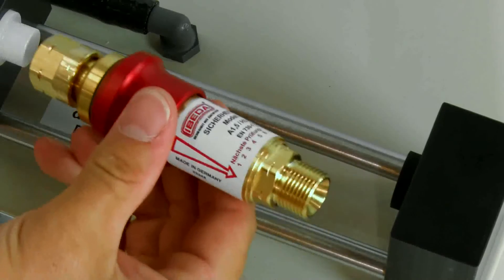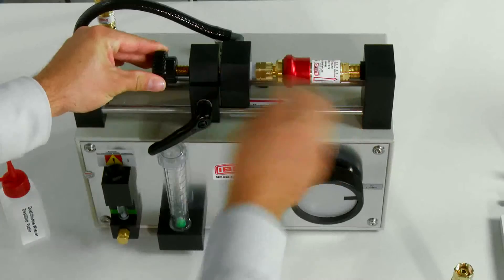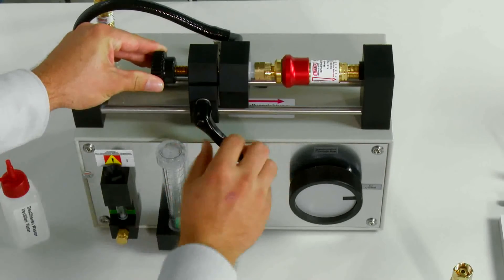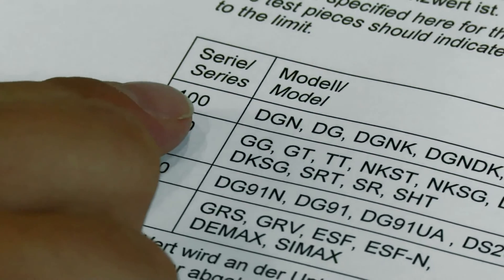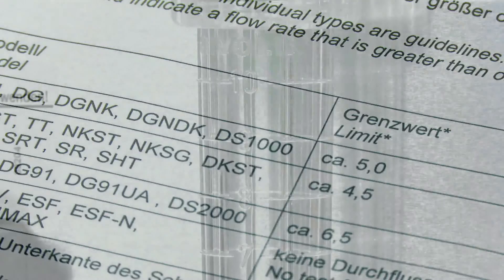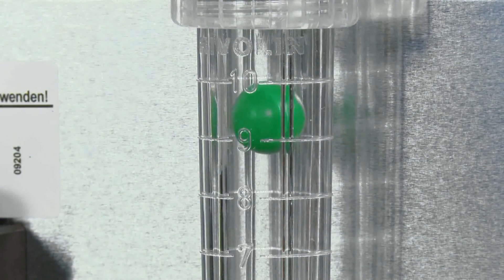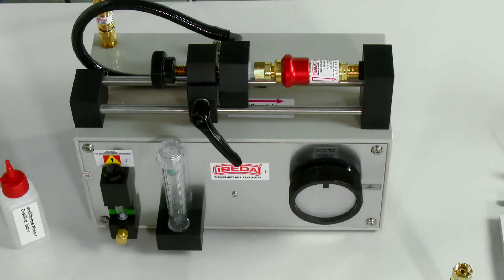The test object is clamped in such a way that its flow direction corresponds to that of the test device. Flow measurement can begin by setting the hand wheel to gas flow. The boundary values for too little flow rate depend upon the particular device under test. Please consult the operating manual for this data. The data refers to the lower edge of the float. The device under test should indicate flow that is larger or equal to the boundary value.